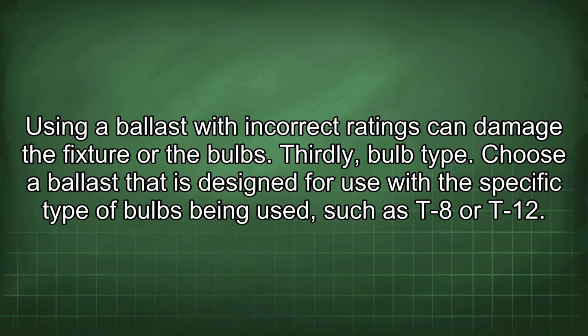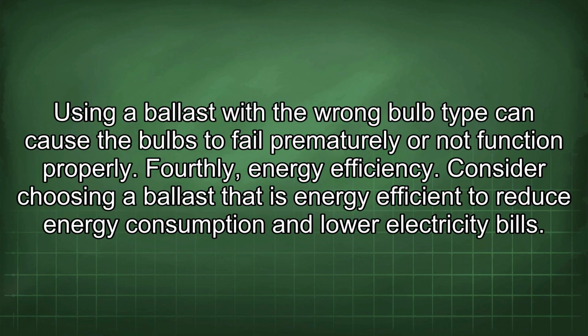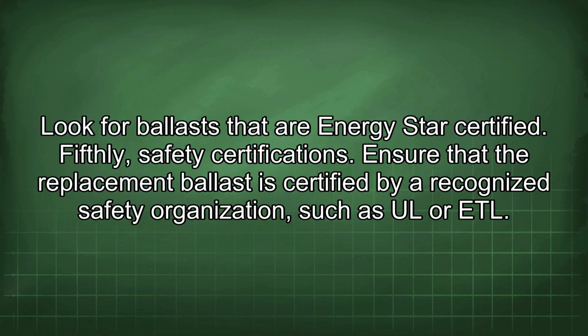Thirdly, bulb type. Choose a ballast that is designed for use with the specific type of bulbs being used, such as T-8 or T-12. Using a ballast with the wrong bulb type can cause the bulbs to fail prematurely or not function properly. Fourthly, energy efficiency. Consider choosing a ballast that is energy efficient to reduce energy consumption and lower electricity bills. Look for ballasts that are Energy Star certified.